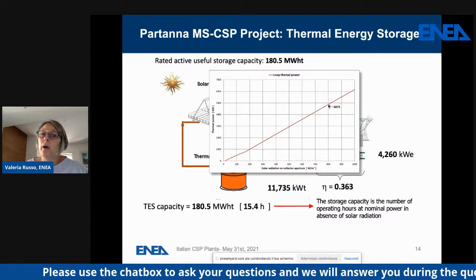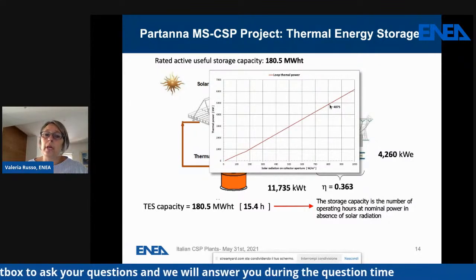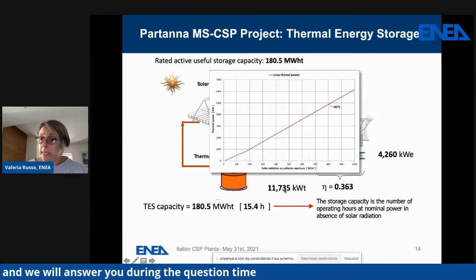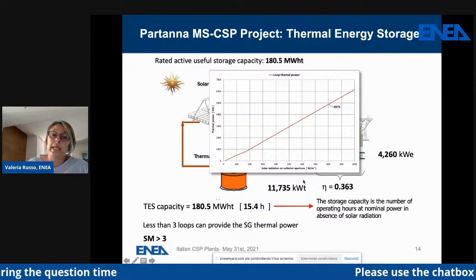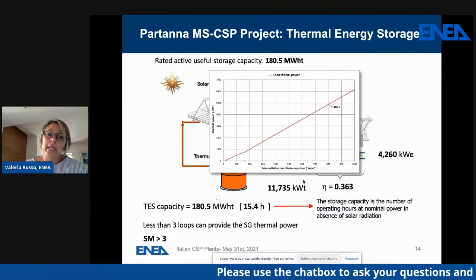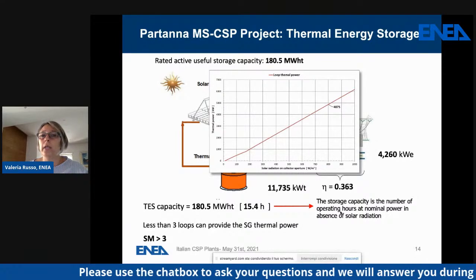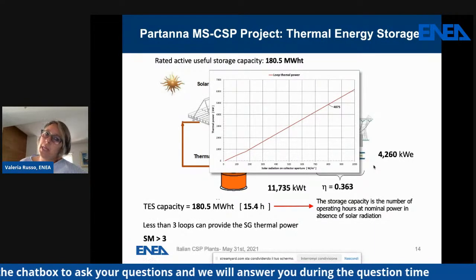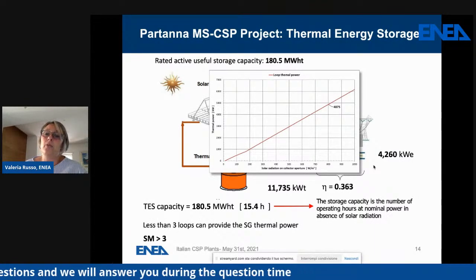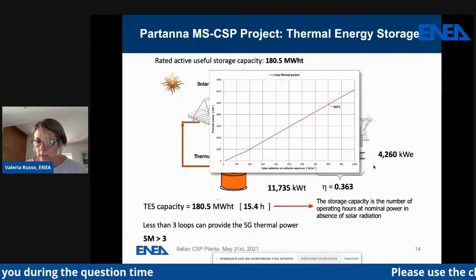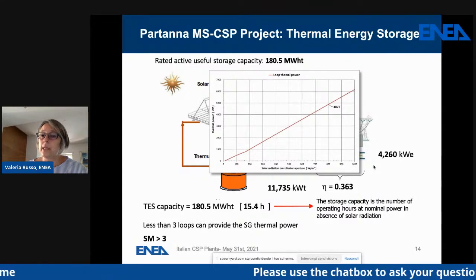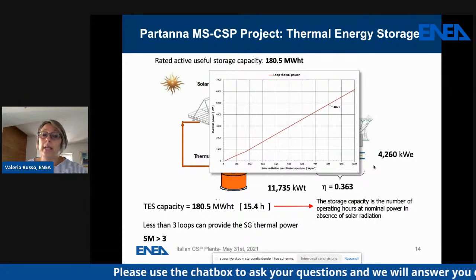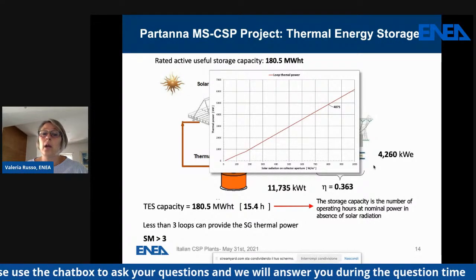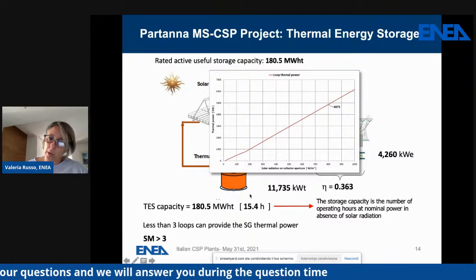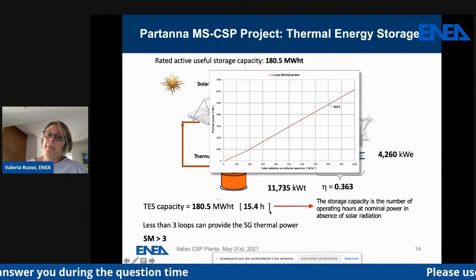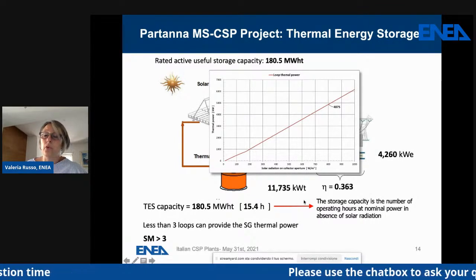So we can say that we need less than 3 loops in order to satisfy the power required by the steam generator. And so in this case, we can say that the solar multiple of the solar field is greater than 3. All the other loops can be used for storing the energy. And then we can define the storage capacity of the thermal storage system as the number of operating hours at nominal power in absence of solar radiation. And in this case, with this dimension of the solar field and this capacity in thermal megawatt, we have a storage capacity equal to 15.4 hours.